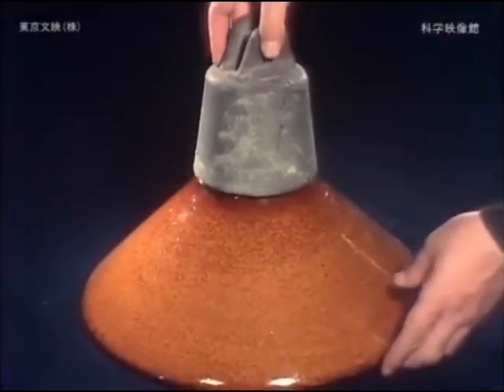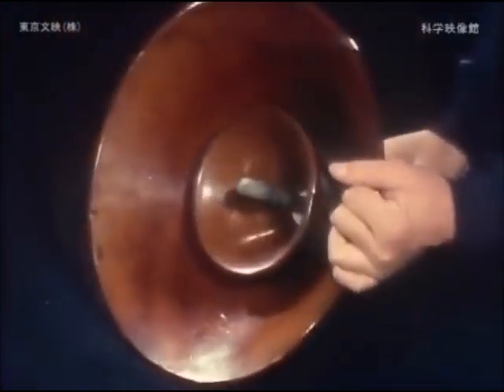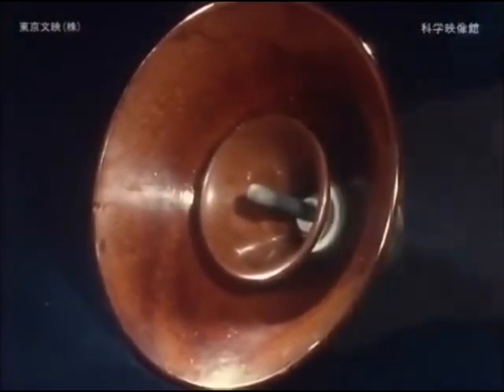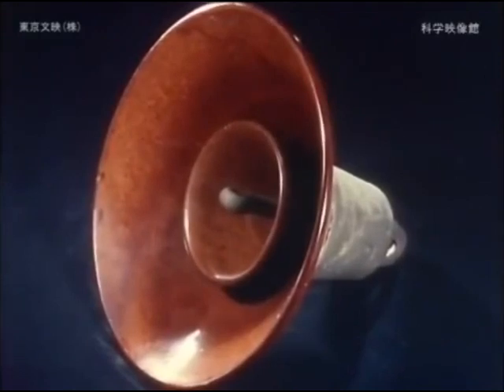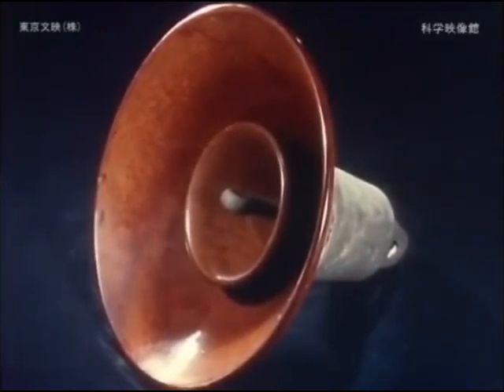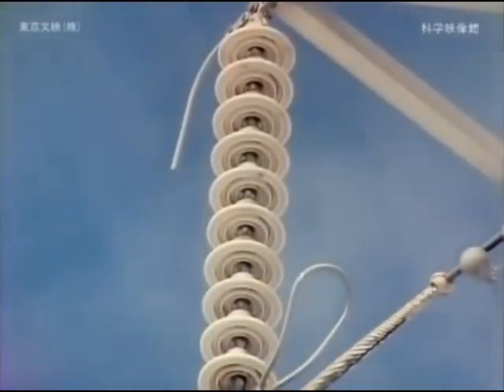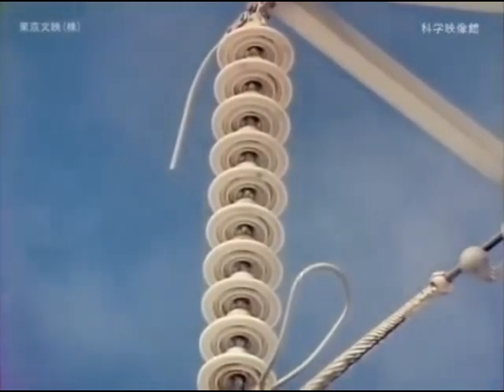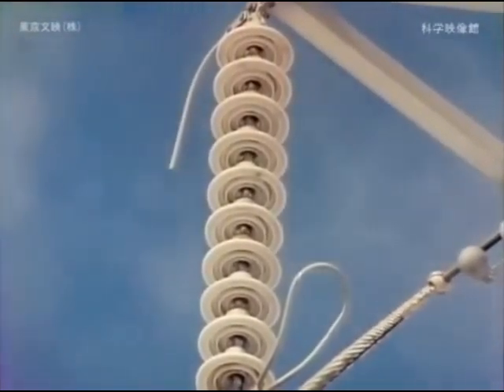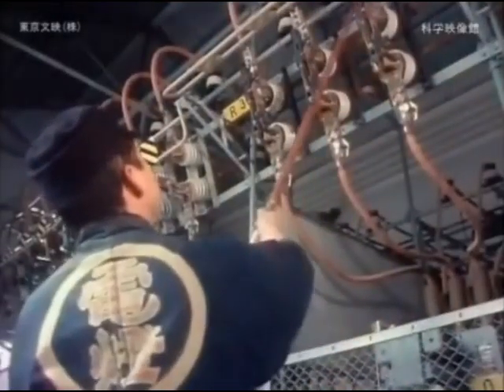One thing that solved this problem is the suspension insulator. As the voltage increases, current leaks or an arc occurs on the surface of the insulator, but the suspension insulator is made to withstand high voltage by lengthening the leakage distance of the current through folds. Moreover, since many can be connected together, it can cope with high voltage.